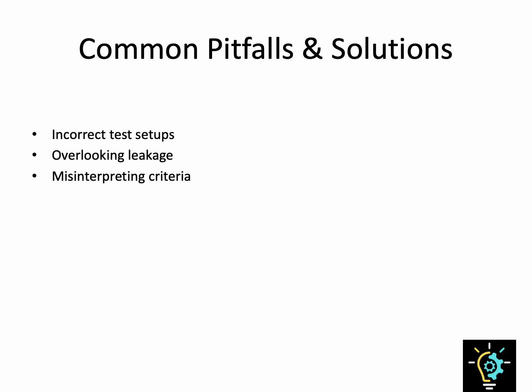No standard is perfect, of course, and some common pitfalls do arise with IEC 62353. One of the biggest mistakes is engineers misapplying IEC 60601 procedures when they're actually supposed to be using IEC 62353. For example, expecting elevated mains or preconditioning can cause confusion. Remember, the goal is safety, not blindly following a checklist. So keeping that mindset helps avoid pitfalls and makes sure IEC 62353 testing adds real value.